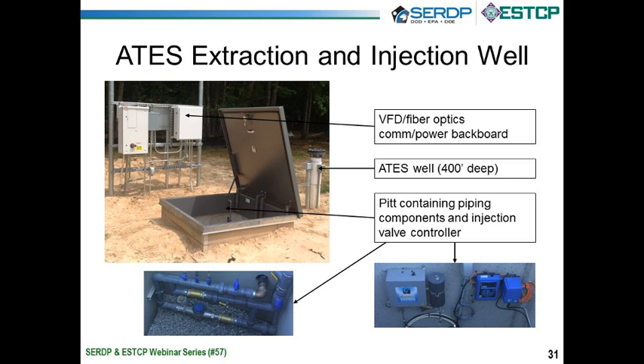The water then flows from that white well underground into this pit. You can see the lid open, and the illustration in the lower left is the water in the bottom right corner coming from the well. It then, depending on whether you're going in or out, passes through a series of pipes. That blue circle you see is the water meter, where we're metering the injected volume of water. And we have temperature sensors and so forth, and then that water exits the pit and heads back to the building. So on the opposite wall of that pit is what you see in the lower right-hand corner.